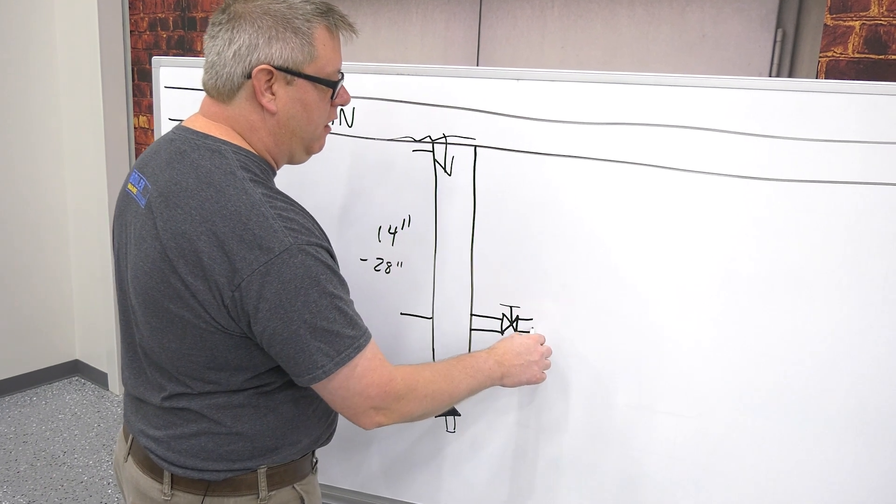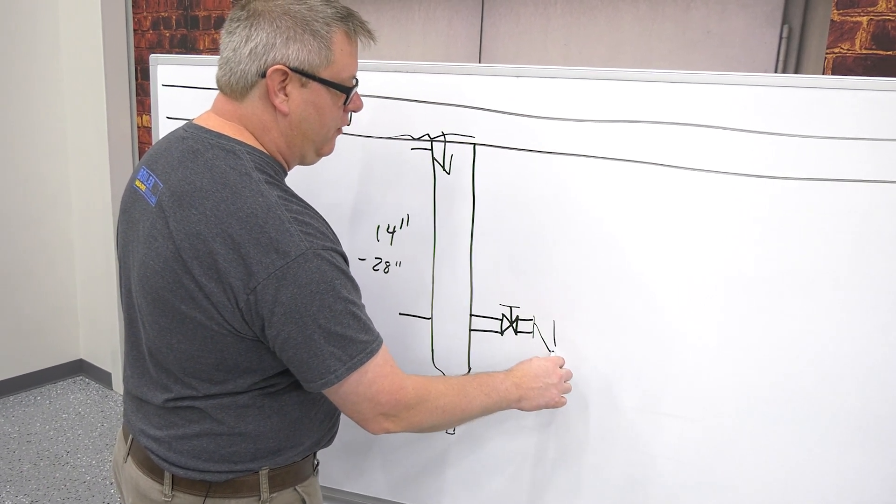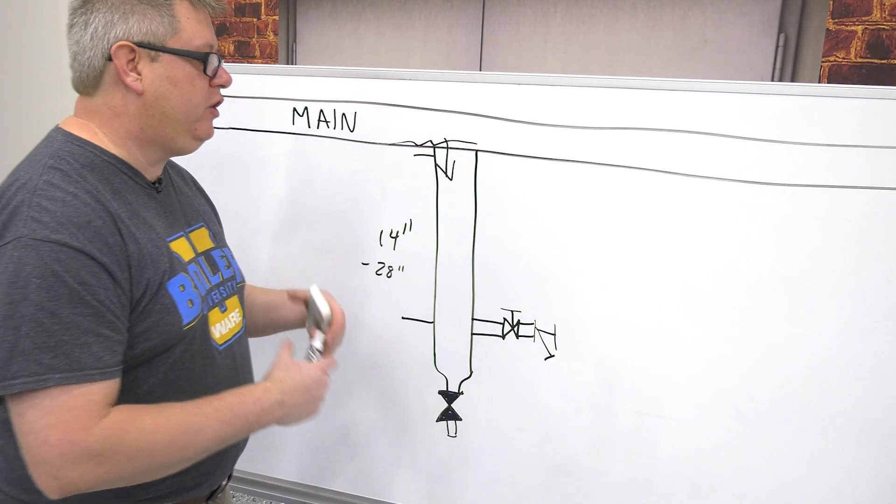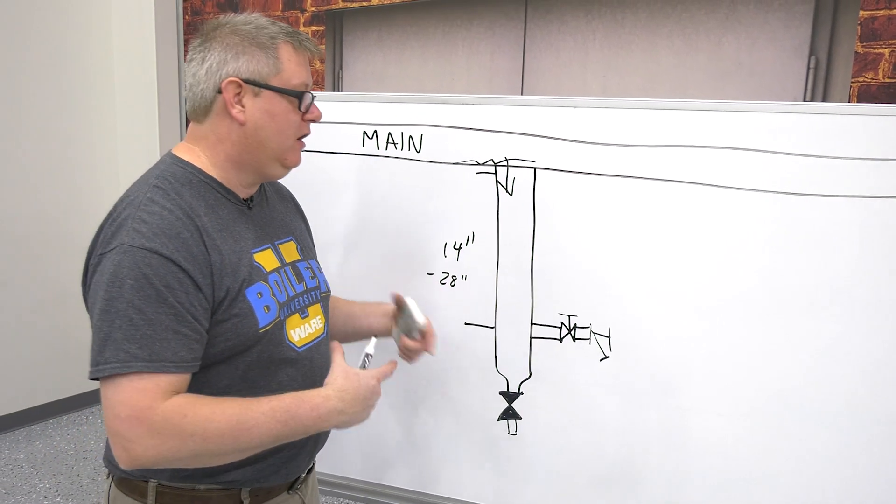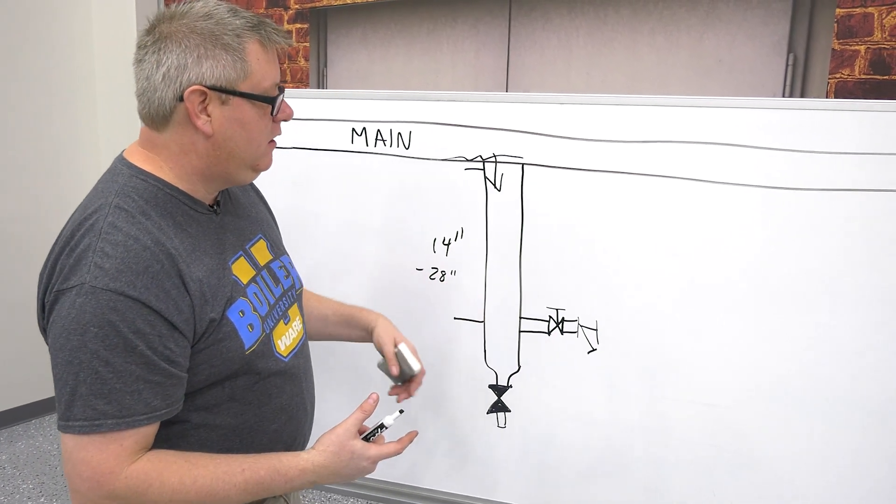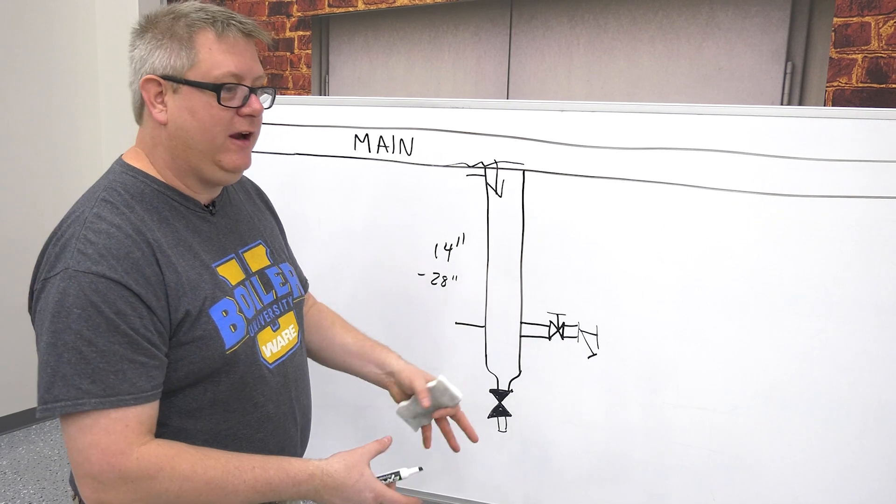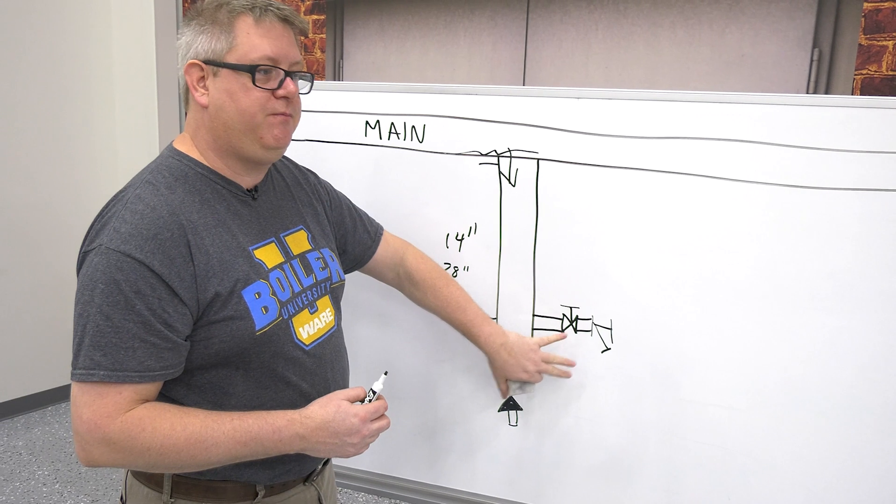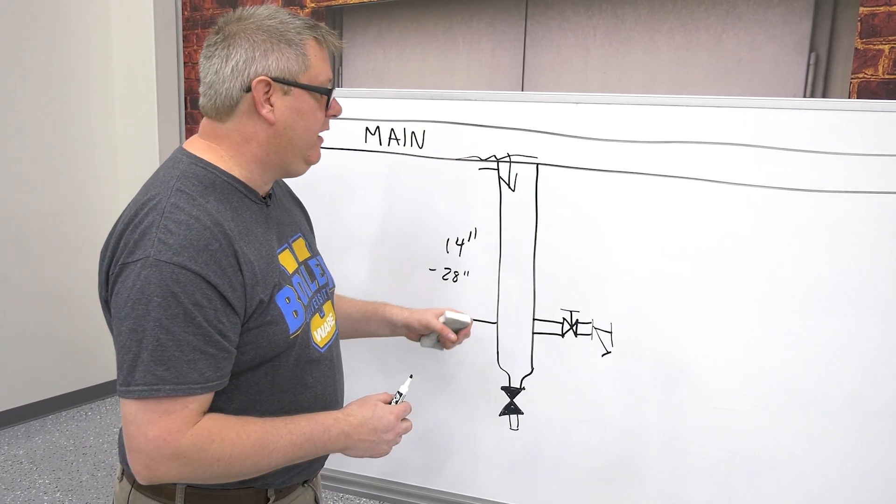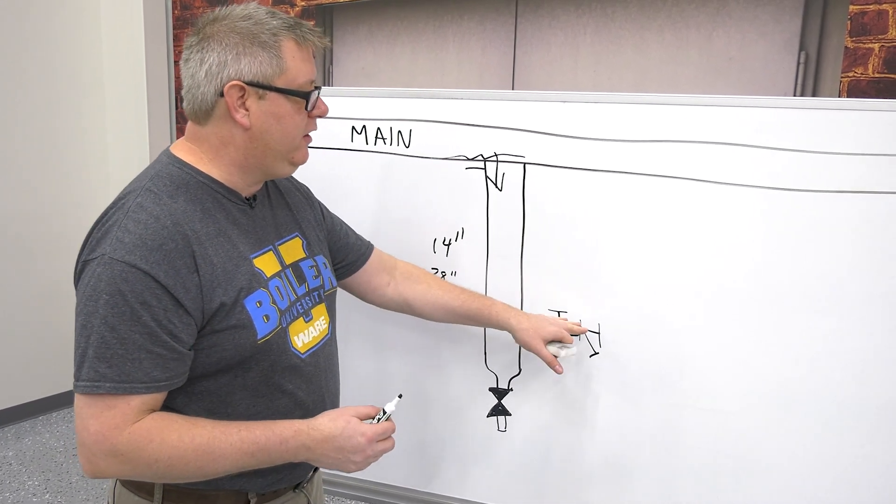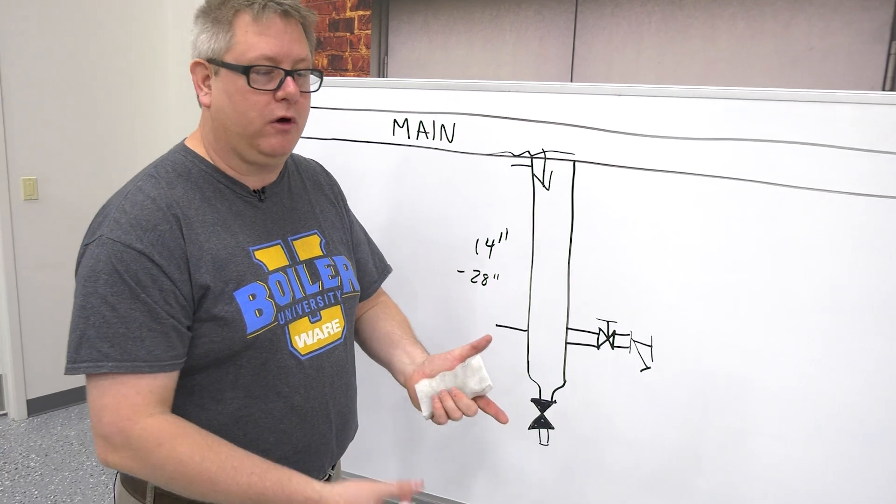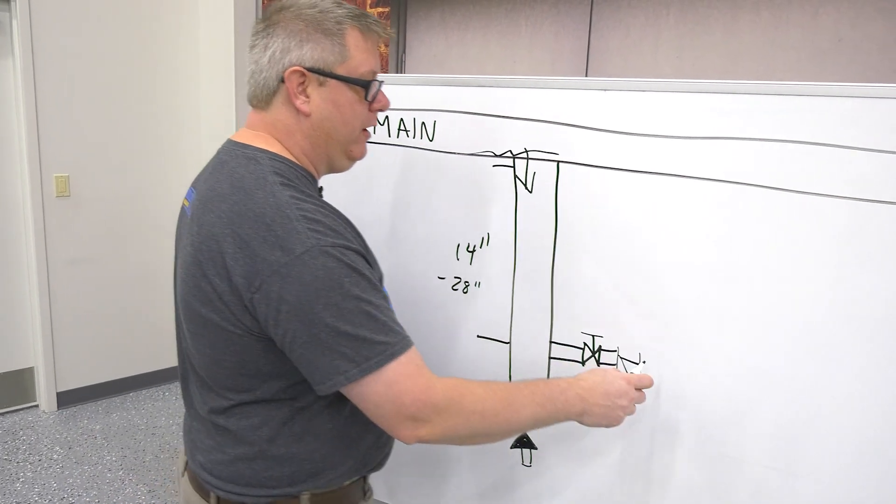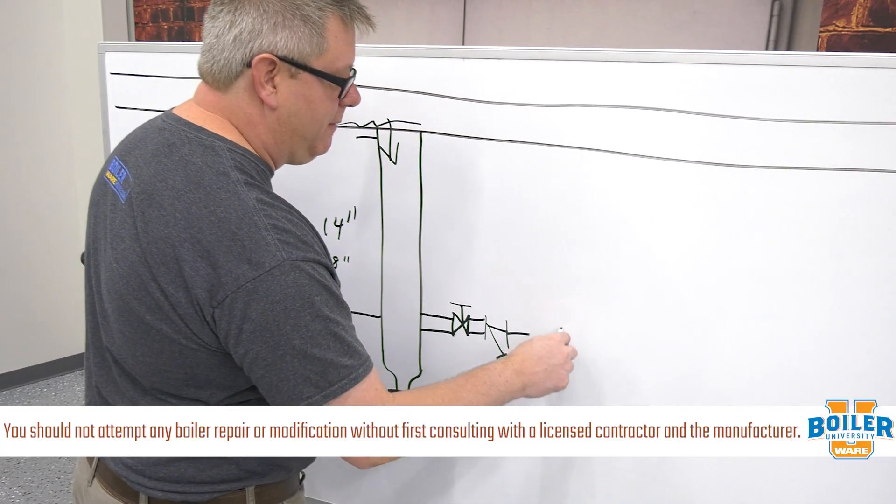After that isolation valve, we want to have a strainer. A strainer protects the trap from debris that comes in, and some traps have strainers integrated. If you're putting in a new drip leg, feel free to use that integrated strainer. If there's an existing strainer, I'm never going to take that out regardless of what type trap I'm putting in. Then we're going to have our trap itself.